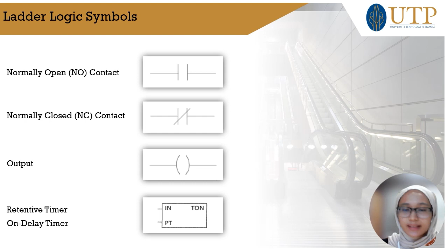The difference between these two timers is in their behavior and application. A retentive timer continues to count time even if the PLC program is interrupted. Therefore, it stores the accumulated time value in a memory location and continues to count when the program is resumed. While an on-delay timer starts counting time when a trigger condition is met, then activates the output after that specified time delay.